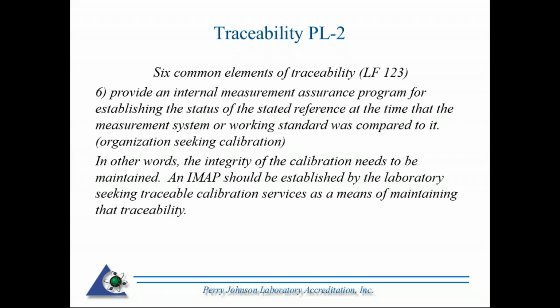So again, you can provide traceable results without being accredited. PL2 recognizes this. However, you can see there are hoops that have to be jumped through. LF-123 has to be filled out, and then they have to provide the objective evidence that I just went through. You have to see the reports of their standards, check out the uncertainty, and assure that they have a measurement assurance program in place.